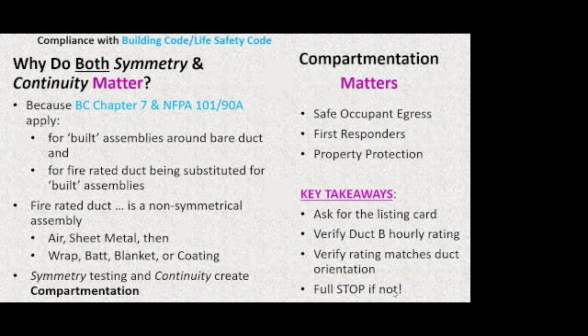So the first thing I'm going to ask you is recognize that when we take the built assembly away from a bare duct, as described by the construction and the code, and we substitute a fire rated duct for that entirety, we now have an assembly that has been tested as an assembly that is the duct and the fire rated assembly all built into one. And it is non-symmetrical like those shaft walls, different materials being attacked in a different order. And that means we need to pay attention to testing both sides and using the lower of the 2 results. And then and only then do we have symmetry and continuity protection for a full compartment. And the way to do that is to verify through the listing card that the duct has duct B.